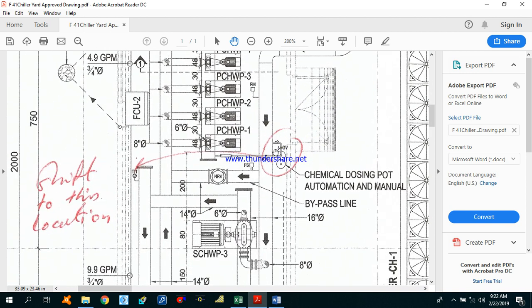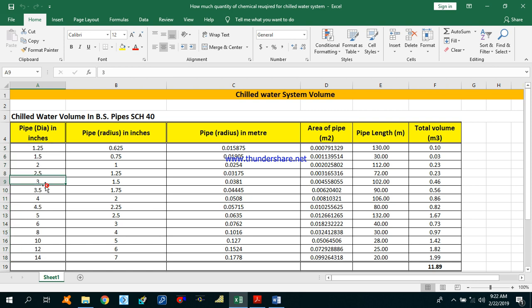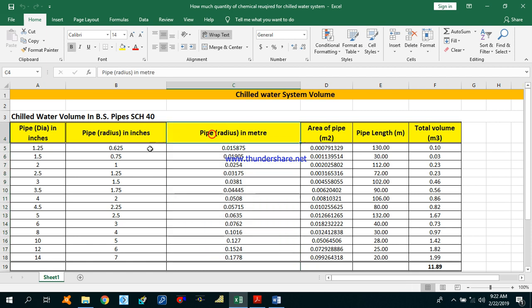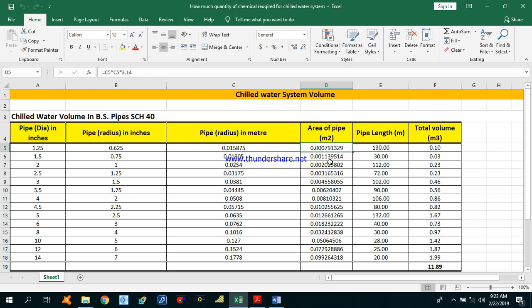This is our chemical dosing pot installed here. So let's start the calculation. This is the Excel sheet. First, you have to write all the piping you have used in your project — all the diameters from your drawings. Then you can convert this into radius, in inches, and this column shows the same radius in meters. This is all the piping we have used in our project, that is 1.25 inches to 14 inches. You have to calculate the area of the pipe for 1.25 inches — it is pi r squared. You can calculate the area of the pipe for each and every diameter.